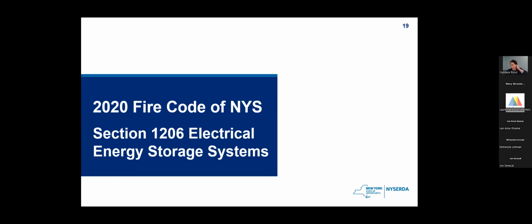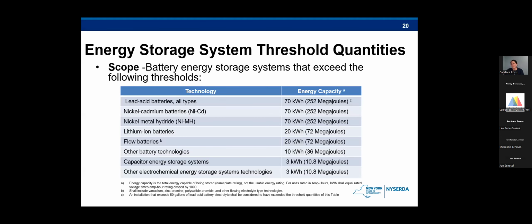So now we'll move into fire safety compliance that is required for non-residential systems, which will include most commercial and utility scale systems. So to kick off this section, we're starting with the scope of the IFC. Basically the scope of this section is relevant for all battery energy storage systems having capacities that exceed the value shown in this table. So really any lithium ion battery exceeding 20 kilowatt hours must comply with this section.